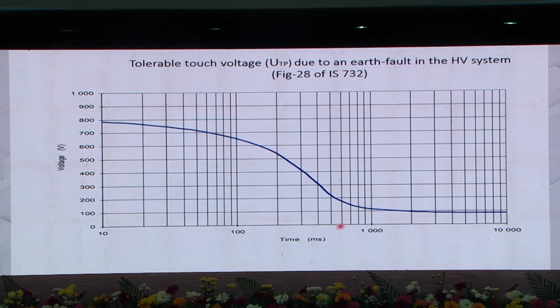So, for example, for 1200 volt, see 1200, and for less than 5 seconds, this will be the value. This is 1 second, 2 seconds, 3 seconds, 4 seconds, 5 seconds. Say somewhere around 70 to 80 volt. So it is very tough to contain the EPR limit below this voltage unless we have a very good earthing system.